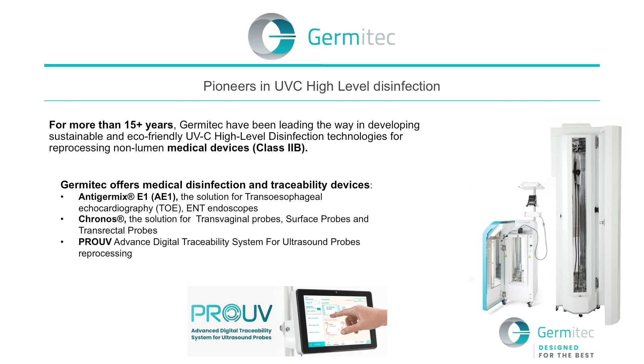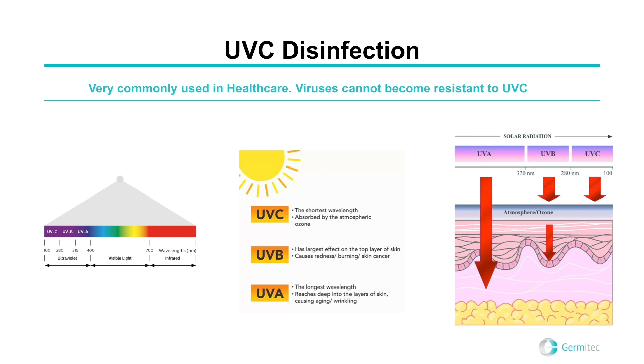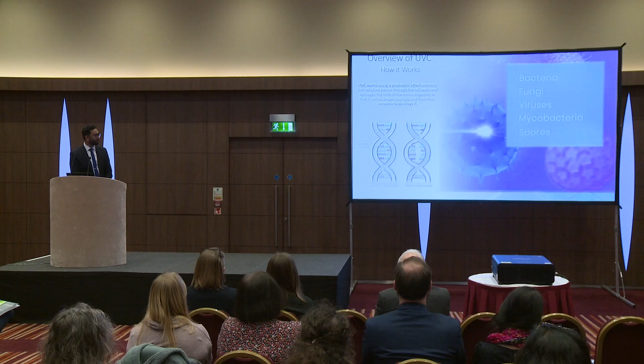So for those of you that aren't aware, UVC disinfection uses UVC light. We all might have heard of UVA and UVB. That's what we apply our sun cream for. But UVC is actually absorbed by the atmosphere, so that's why we recreate it. And the reason for that is UVC uses a photolytic effect, whereby the radiation passes through the cell walls and damages the thymine bases within DNA. This stops it replicating and therefore destroys it, making it a very effective form of high-level disinfection, which viruses cannot become resistant to. So we harness this technology within our products with a special design that allows a proper illumination and efficient exposure to the medical device, which causes no shadowing.